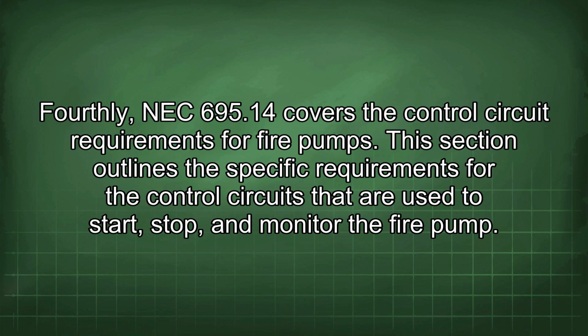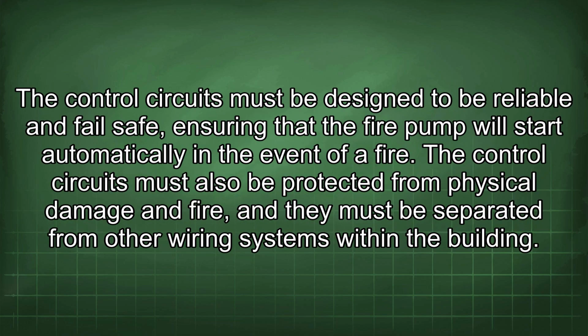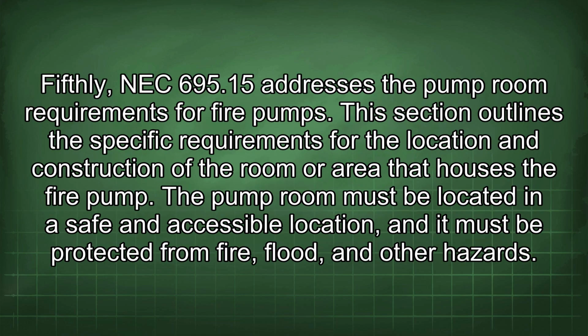Fourthly, NEC 695.14 covers the control circuit requirements for fire pumps. This section outlines the specific requirements for the control circuits that are used to start, stop, and monitor the fire pump. The control circuits must be designed to be reliable and fail-safe, ensuring that the fire pump will start automatically in the event of a fire. The control circuits must also be protected from physical damage and fire, and they must be separated from other wiring systems within the building.